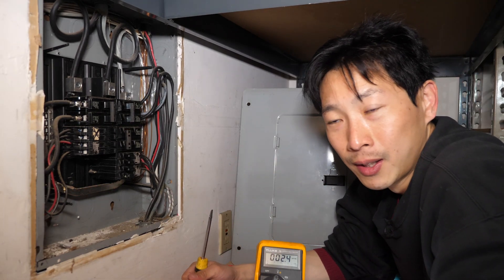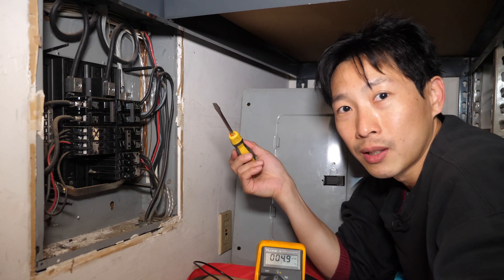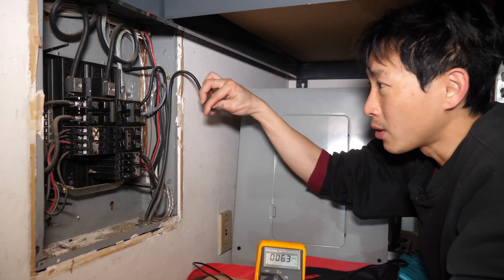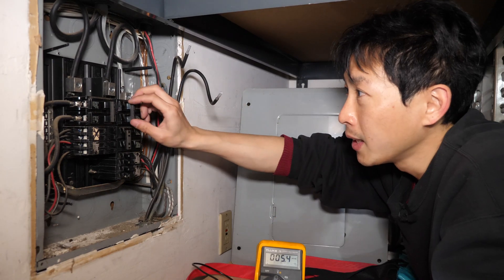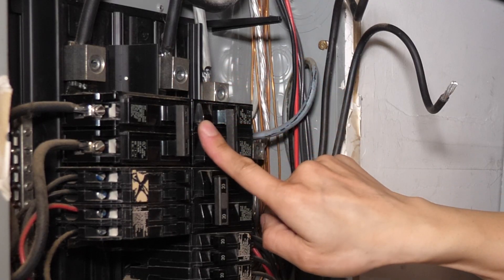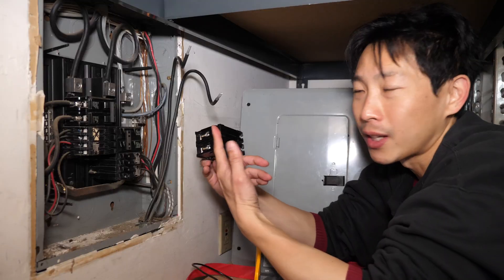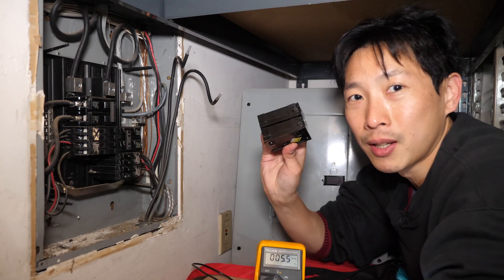Although I measured safe levels, out of precaution I'm still not going to touch it. I'll use this screwdriver with a rubber handle to open the terminals up, pull these wires out — these are not live voltages. I'm putting it over here, being careful not to touch it just out of precaution. To remove the breaker, you firmly pull it on this side — it locks down on one side, so you kind of pull it like this and the whole thing loosens up. There's a catch that locks onto one of the bars, and it snaps out.